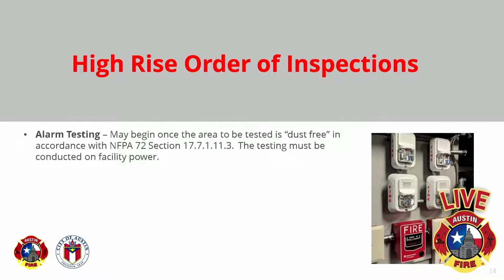So alarm testing. This is the bulk of our testing at the end. And this is something that we typically do alongside the Special Inspections Agency. Because we're requiring that approved report, it's very common that people want to start testing before we are NFPA 72 Chapter 17 compliant. Chapter 17 in NFPA 72 states that where detection is not required during construction, devices will not be added until it is a dust-free environment. Now, dust-free is a pretty stringent term, and we're willing to look at it, depending on the stage of your construction. But for the most part, we need a clean environment so the alarm companies can snap in their devices, and we can test so they're not being degraded along the way.